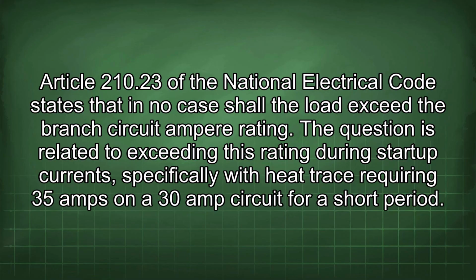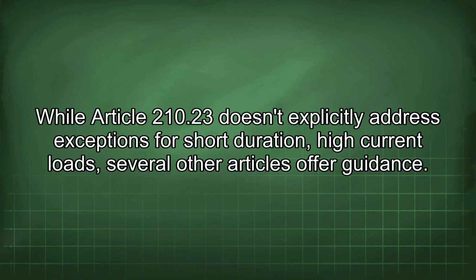Article 210.23 of the National Electrical Code states that in no case shall the load exceed the branch circuit ampere rating. The question is related to exceeding this rating during startup currents, specifically with heat trace requiring 35 amps on a 30 amp circuit for a short period. While Article 210.23 doesn't explicitly address exceptions for short duration high current loads, several other articles offer guidance.